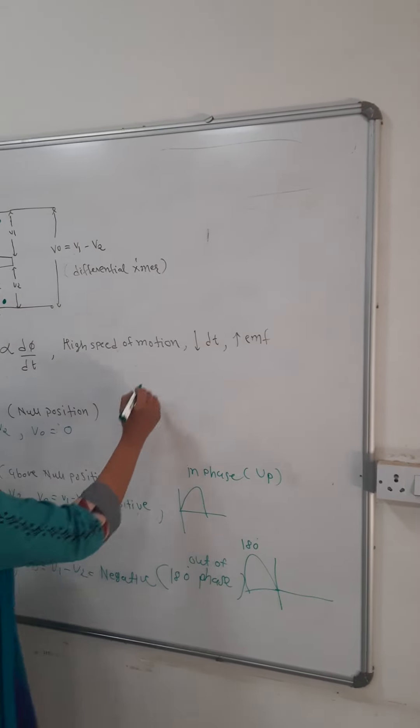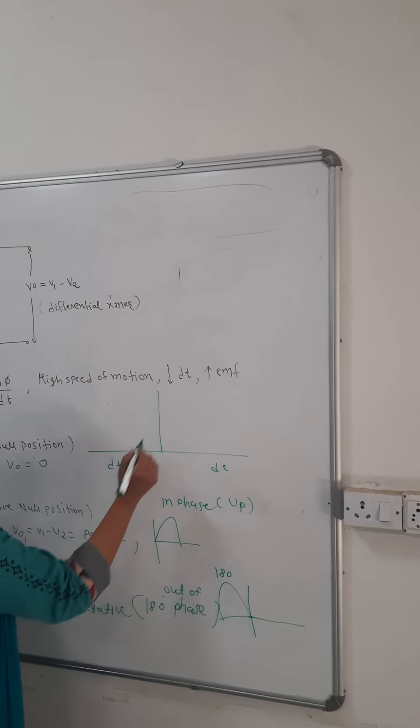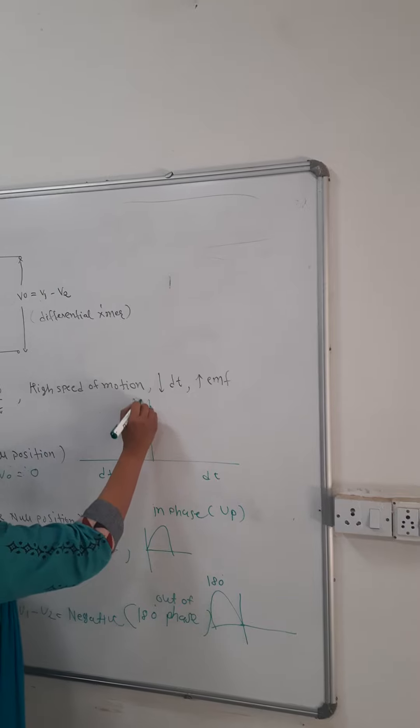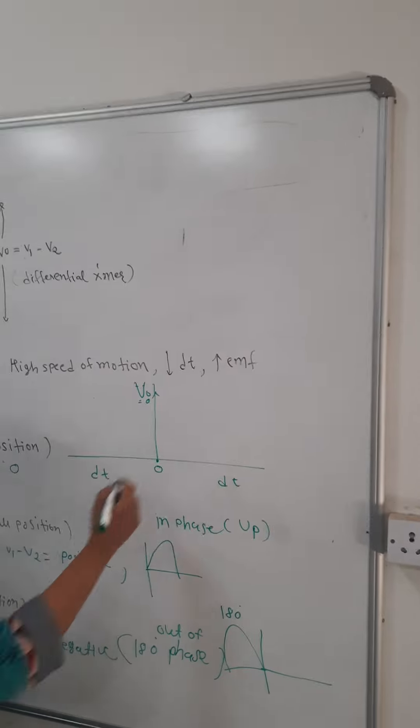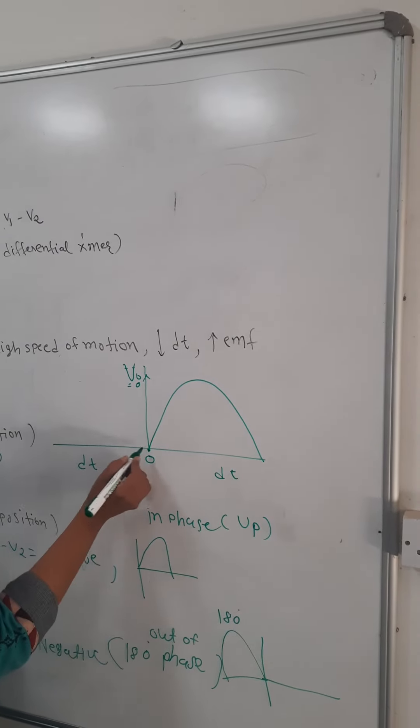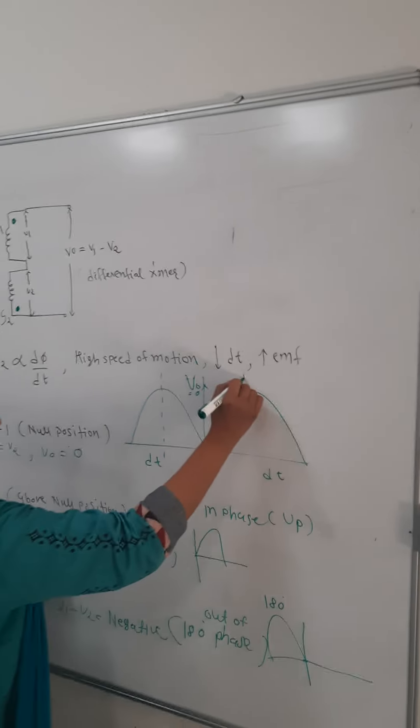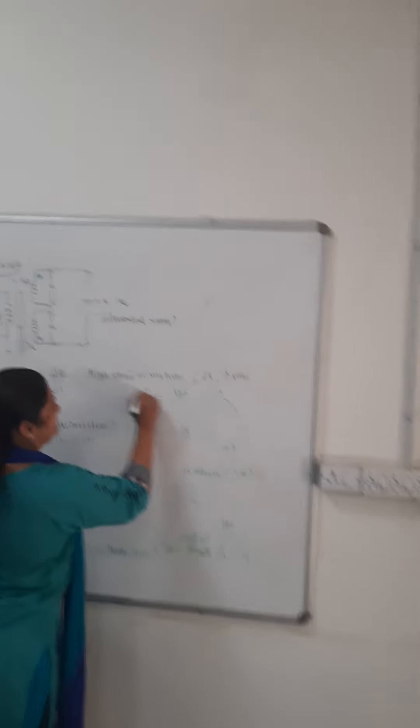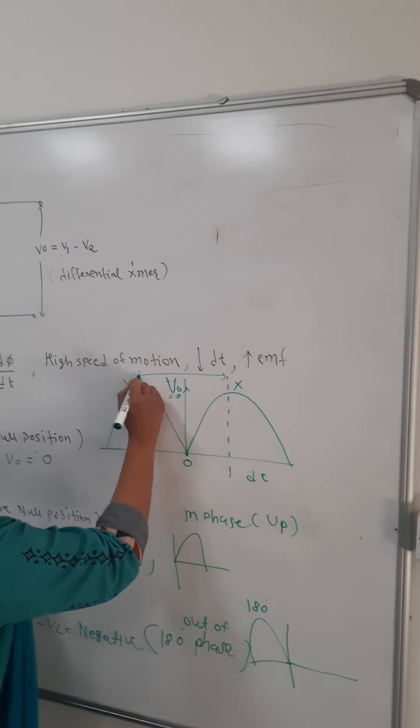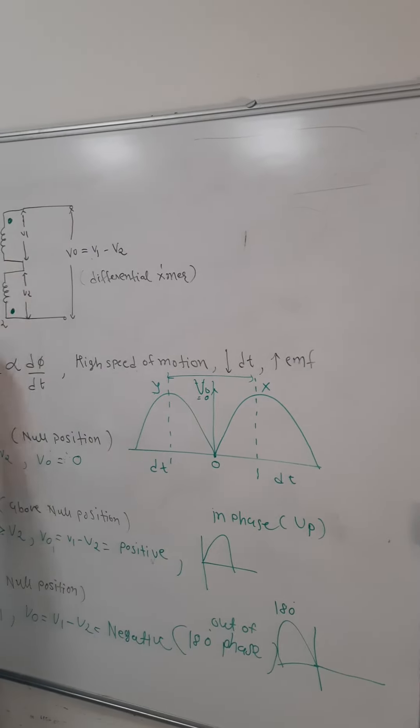Now, let me combine all three cases together in the graphical form, displacement vs voltage. When at null position, we have V0 at this 0 position. This is our 0 position. For case number 1, this is the positive half cycle. This is the negative half cycle for second case. It means we have this range of x to y. From x to y, this is all about the range of operation. Maximum deflection from upper side to lower. This is x to y. So in that way, we can verify LVDT work.